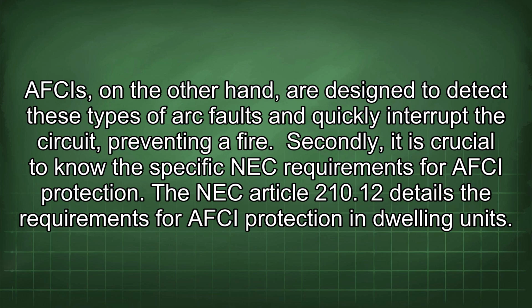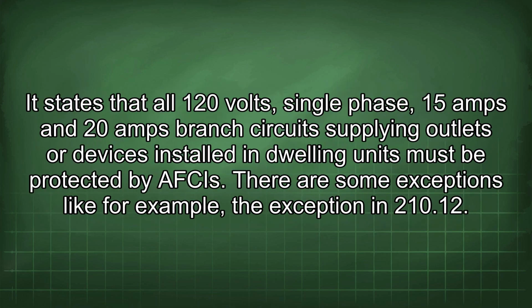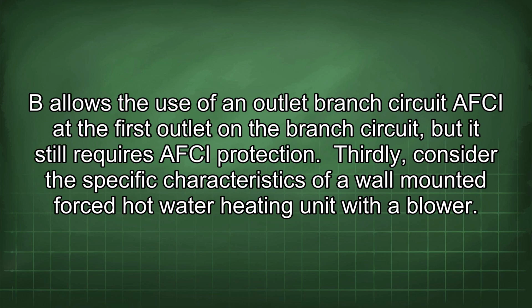Secondly, it is crucial to know the specific NEC requirements for AFCI protection. NEC Article 210.12 details the requirements for AFCI protection in dwelling units. It states that all 120 volt, single-phase, 15 amp and 20 amp branch circuits supplying outlets or devices installed in dwelling units must be protected by AFCIs. There are some exceptions, for example the exception in 210.12, which allows the use of an outlet branch circuit AFCI at the first outlet in the branch circuit, but it still requires AFCI protection.